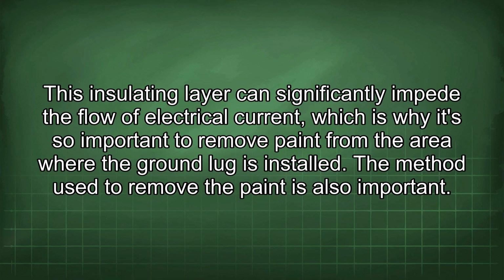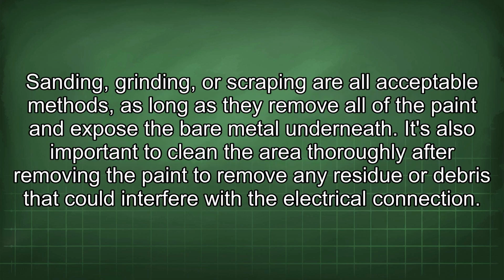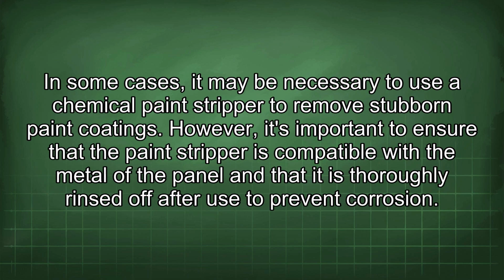The method used to remove the paint is also important. Sanding, grinding, or scraping are all acceptable methods, as long as they remove all of the paint and expose the bare metal underneath. It's also important to clean the area thoroughly after removing the paint to remove any residue or debris that could interfere with the electrical connection. In some cases, it may be necessary to use a chemical paint stripper to remove stubborn paint coatings. However, it's important to ensure that the paint stripper is compatible with the metal of the panel and that it is thoroughly rinsed off after use to prevent corrosion.